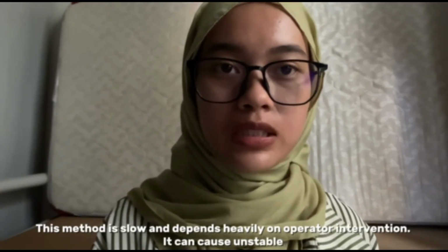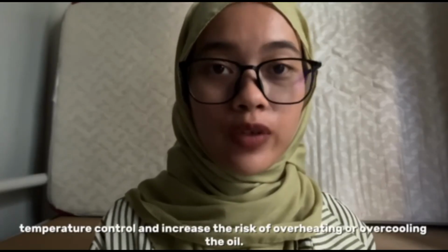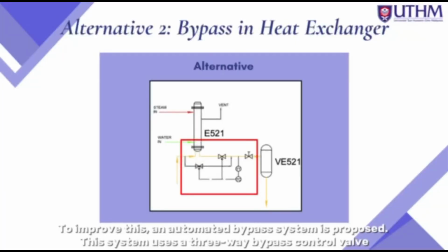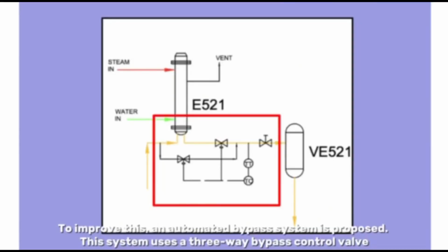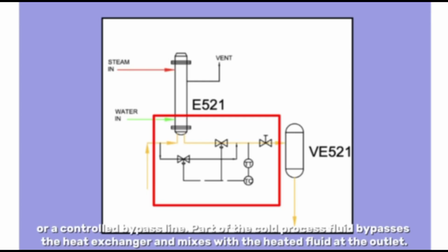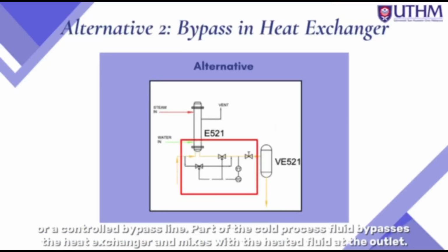It can cause unstable temperature control and increase the risk of overheating or overcooling the oil. To improve this, an automated bypass system is proposed. This system uses a three-way bypass control valve or a controlled bypass line. Part of the cold process fluid bypasses the heat exchanger and mixes with the heated fluid at the outlet.